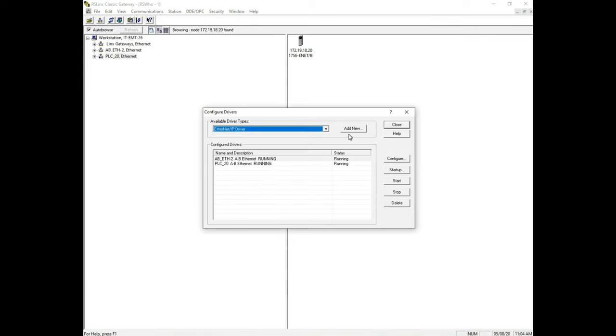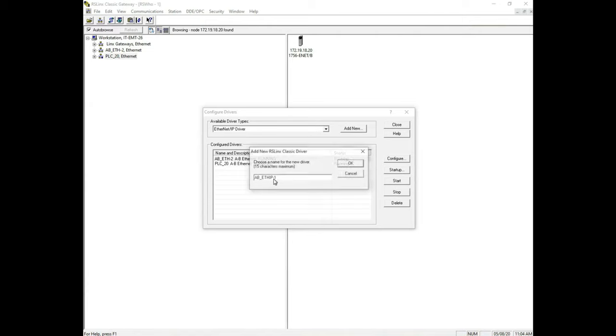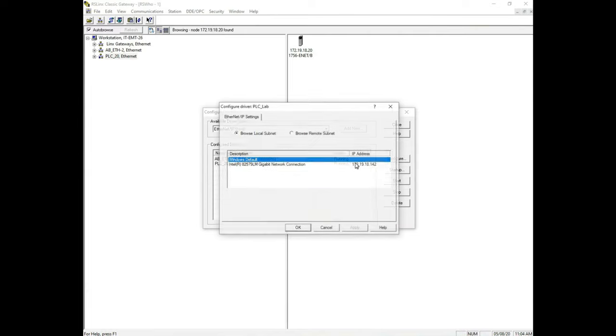Here we're going to select Ethernet IP instead of just Ethernet. Now you're going to see something different here. I hit add new and it wants me to name it again. And instead of one PLC, since this is my whole lab, I'm going to name this PLC underscore lab. Just so I know what that is. Now when I hit OK, this is where you're going to see the difference. Notice I don't have a place to enter an address in. That's because I don't enter address. Notice up here it's going to automatically browse my local subnet and it's going to pull in everything that I can communicate with. So I hit OK.